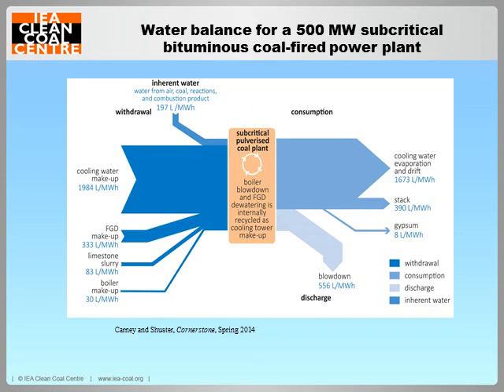Right, I've included this figure to give you an indication of the amount of water that is withdrawn from a water source and consumed within a power plant. It is for a 500 megawatt subcritical plant firing bituminous coal. The plant layout is basically the same as that shown in the previous slide. As you can see, the cooling system, which is a wet cooling tower, consumes the most water, followed by the FGD scrubber, which here employs a wet limestone process.